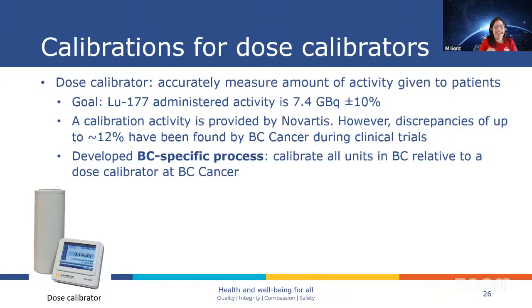And Novartis, who's the manufacturer for Pluvicto, they can give us calibration activities that they send to us. However, because BC Cancer had been doing this for clinical trials for a long time, BC Cancer noticed that the calibration activities that were coming from Novartis were actually not well calibrated. Like they had errors in their activities of up to 12% sometimes, which clinically we can't use for patients. If the way Novartis is calibrating their activities is not correct, then we can't have those kinds of errors with what we give to patients. So in short, we didn't quite trust what Novartis was sending us.